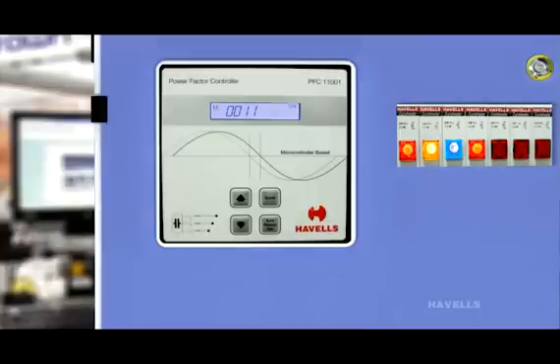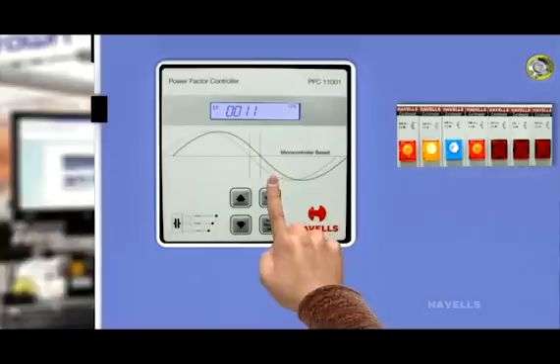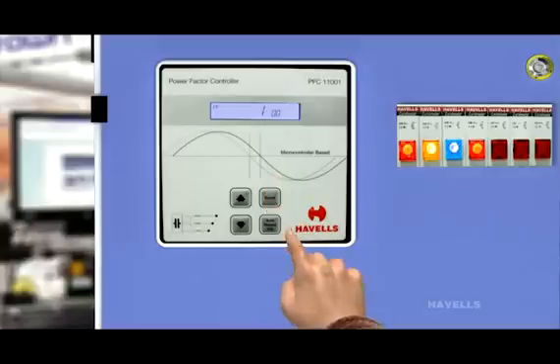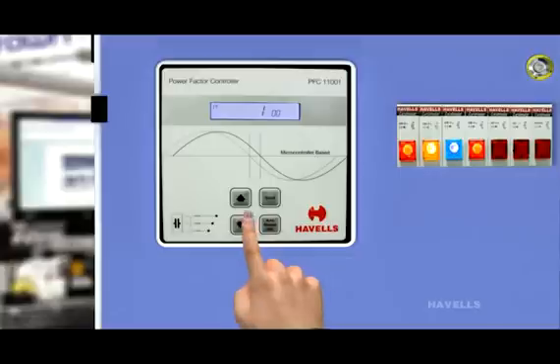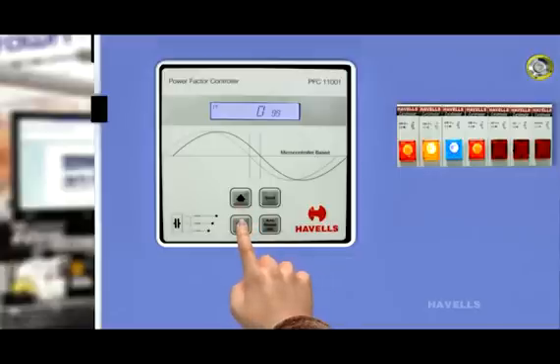Press scroll switch again. Controller shows the target power factor on LCD, which is unity. Through up and down switch, target PF can vary from 0.8 lag to unity.